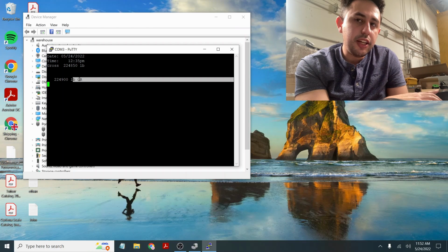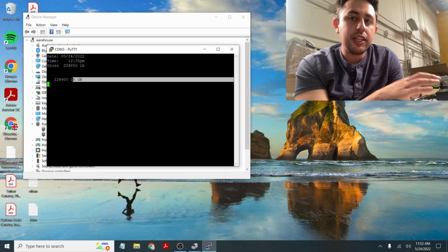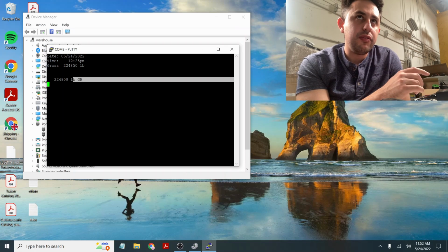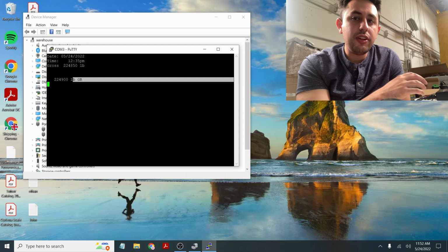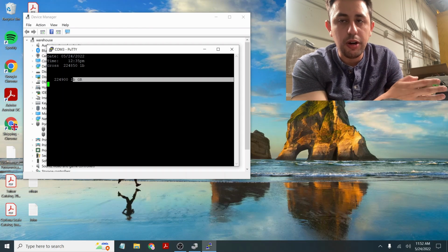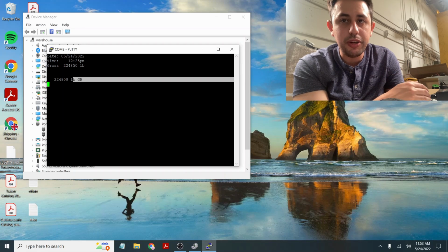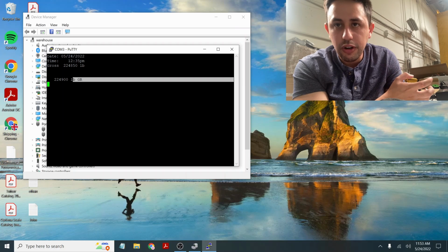So if your indicator, when you press capital P, is not showing the date, time, and gross, then the indicator is the issue, and it will not print. If you press capital G or capital R and it does not show anything at all, then the software itself will not even open. So if you have any problems where the software can't even open, or you make sure the COM port is correct and it still does not print, then most likely the indicator, the C18 setting, yes, is 3, but maybe the firmware on it changed.